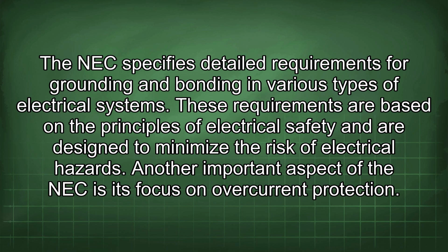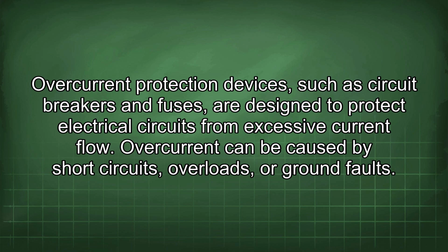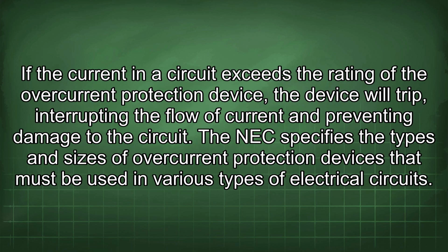Another important aspect of the NEC is its focus on overcurrent protection. Overcurrent protection devices, such as circuit breakers and fuses, are designed to protect electrical circuits from excessive current flow. Overcurrent can be caused by short circuits, overloads, or ground faults. If the current in a circuit exceeds the rating of the overcurrent protection device, the device will trip, interrupting the flow of current and preventing damage to the circuit.